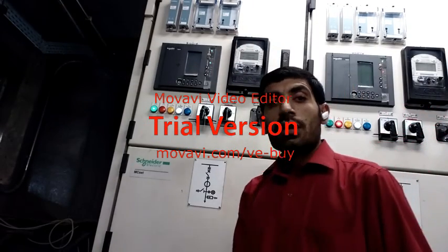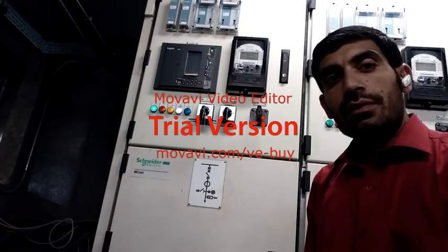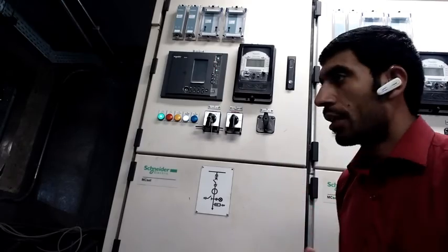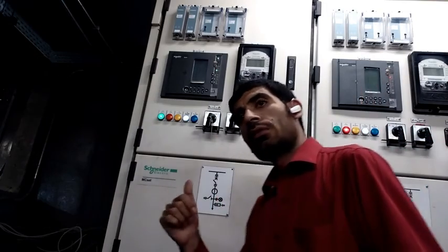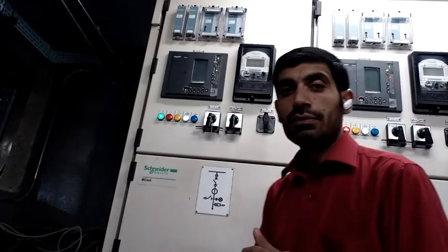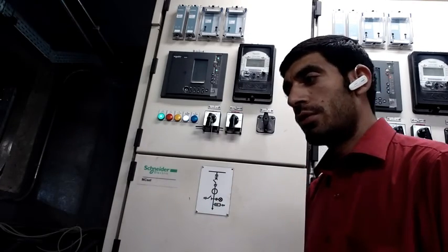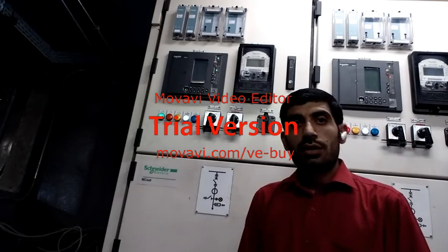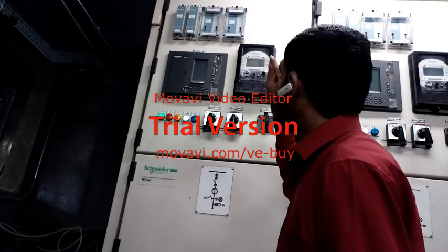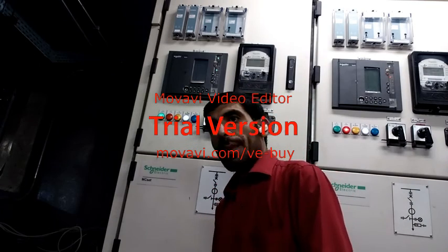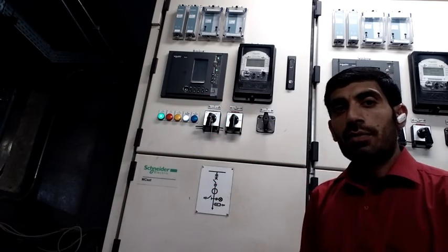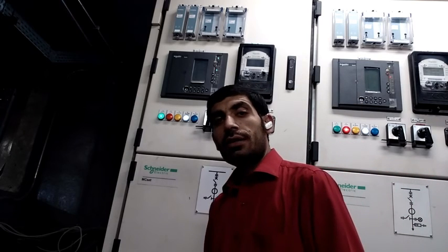So how do we test this relay? We test this relay through Freja. We inject rated voltage and check the timing of this relay, how much time it takes for closing and for opening. For tripping timing we test through Freja. We inject 125 volts on this auxiliary relay coil and check timing through binary contacts. And then we check the pickup voltage and drop off voltage.